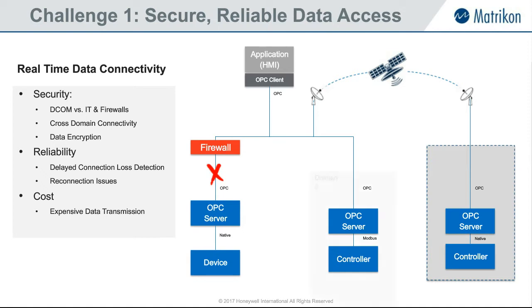If you create another domain, because you're talking across different domains, again, that causes issues if you're using straight OPC. And of course, if you get some kind of atmospheric interference or all sorts of issues that can come up, well, then you also lose your connectivity remotely. Now, we can't control the weather or things that will cause interference for the transmissions.